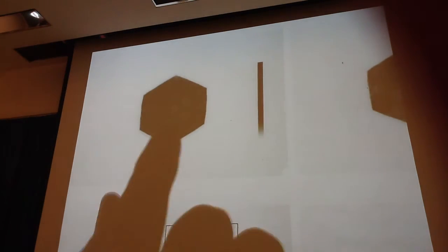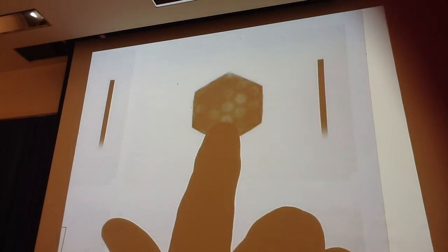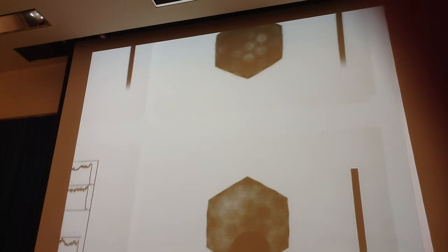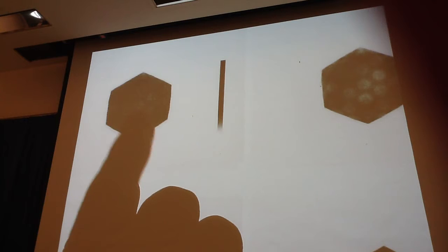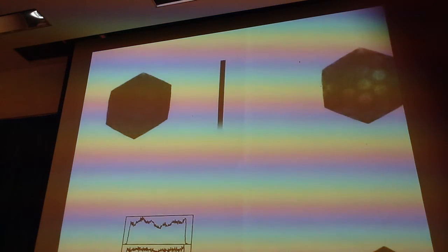Now, once in a while, what we do is some off-peak images. Okay, this is with the cobalt setting. This is with technetium. And then this one here is xenon. Okay? What we're trying to do is, can you guys see the pattern of the PM tubes there? Okay, sometimes they get out of adjustment.